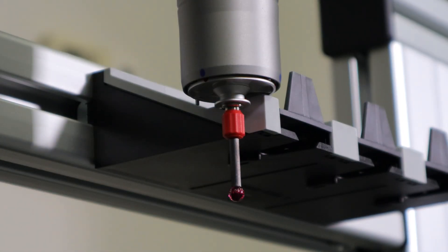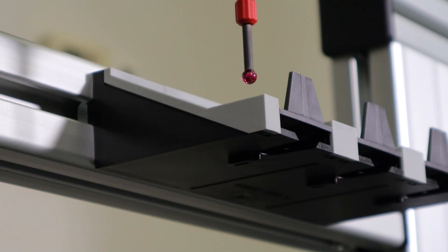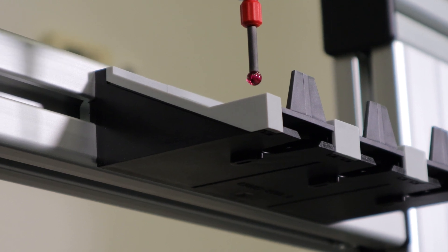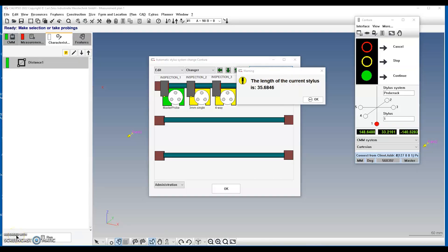Once you've probed it using the adapter plate, raise the stylus and take a point in the same location with the ruby. This process determines the length of your stylus. The length should be between 35 and 36 millimeters.